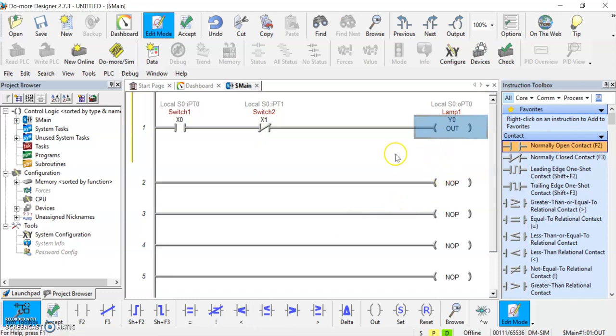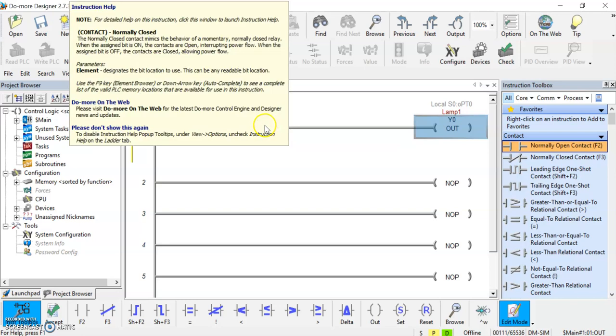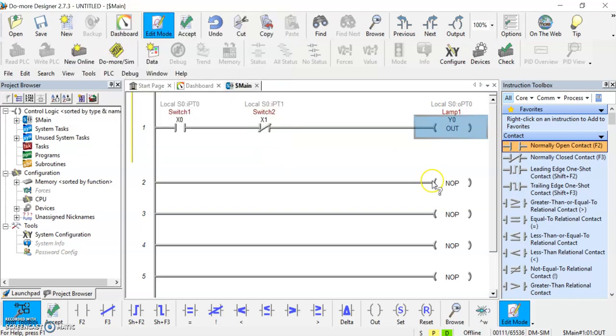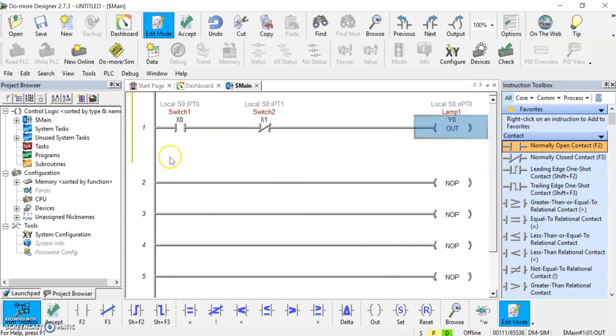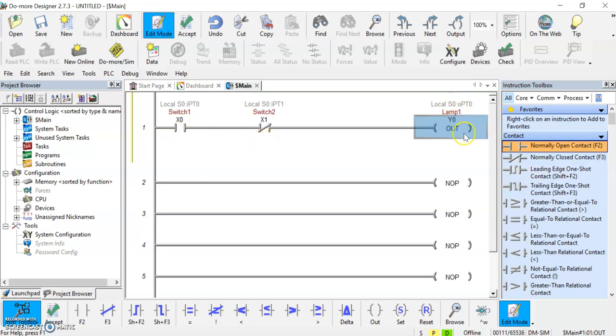If you're ever curious about what the actual instruction does, if you hover over it, it does tell you exactly what it's doing. This just gives you some extra information. Now these would be what we refer to as an AND set of instructions here. This and this have to be in their assigned state in order for this to go true. So that's an AND statement.